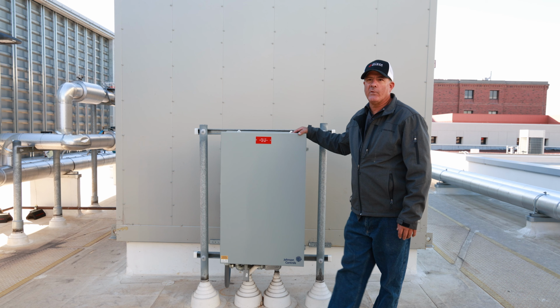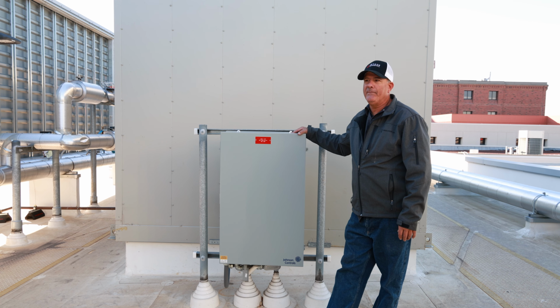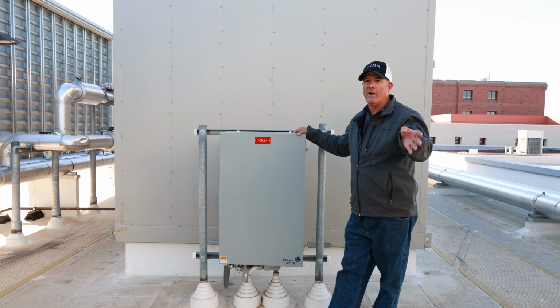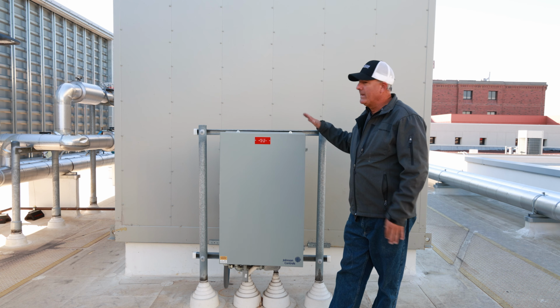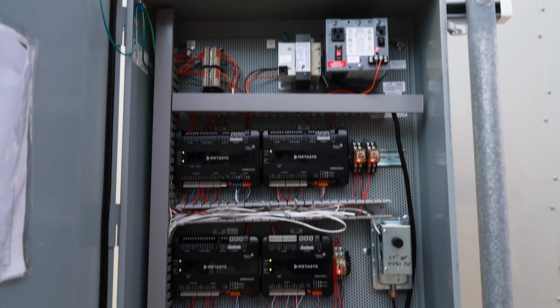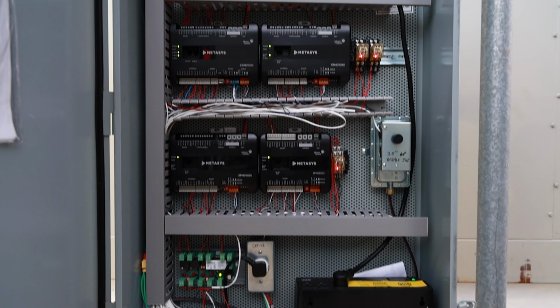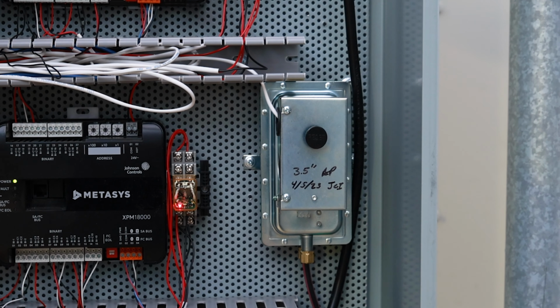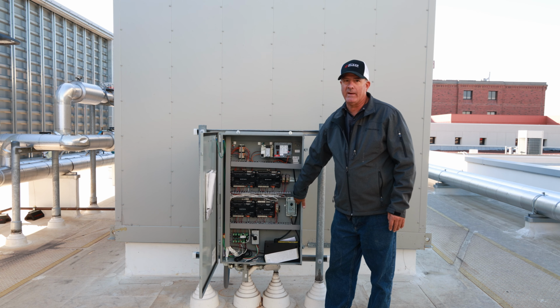This is your temperature control panel for air handler unit 1. They're exactly the same. There's one opposite of me for air handler 2. Inside this temperature control panel is located your high duct static limit. So if you need to reset, it's right here.